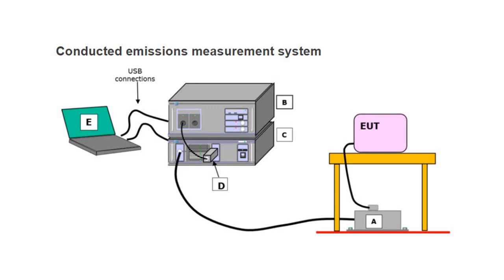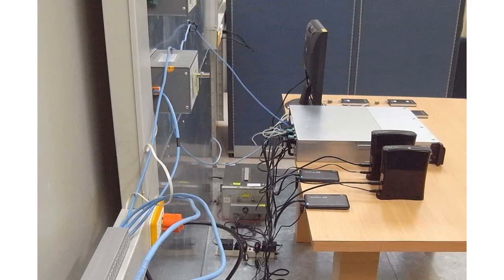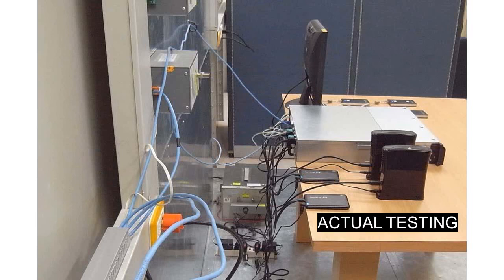High frequency conducted measurement: conducted emission is any emission transported from equipment to the environment along cables. The main emphasis in measuring line conducted emission is placed on the AC mains input of the EUT, though other interface ports are becoming more important, like telecom and network ports on information technology equipment.